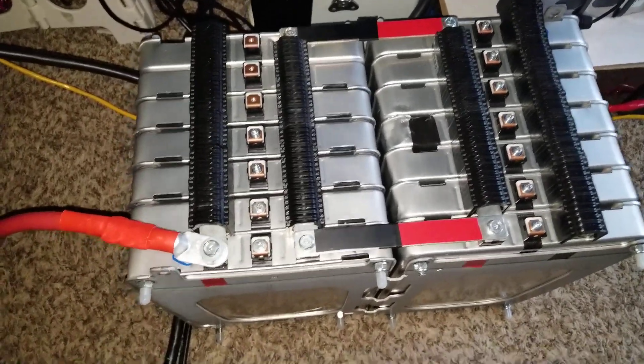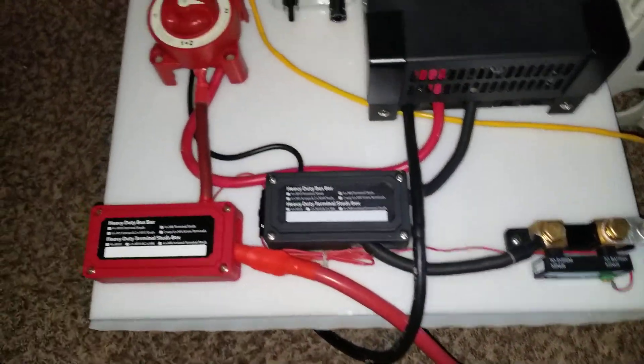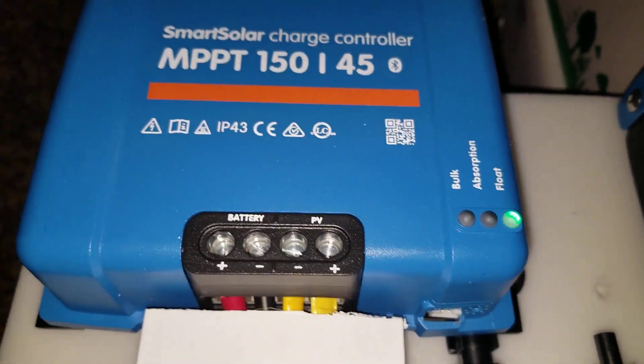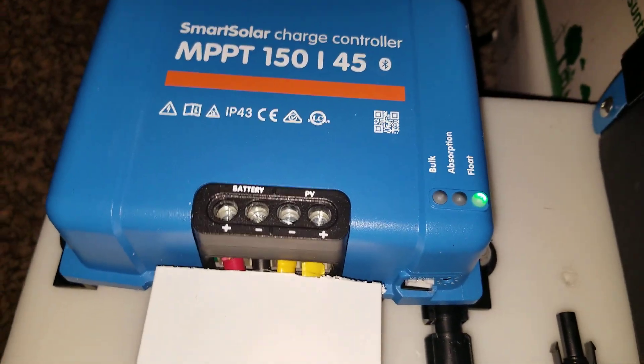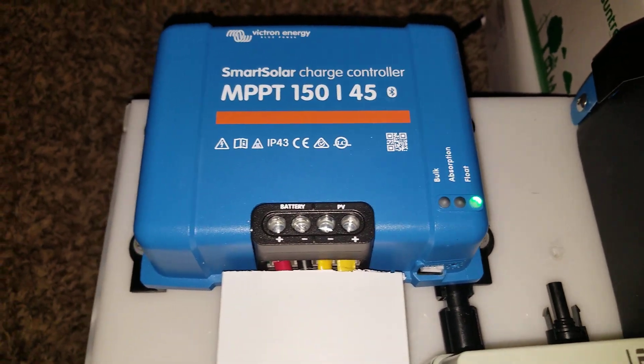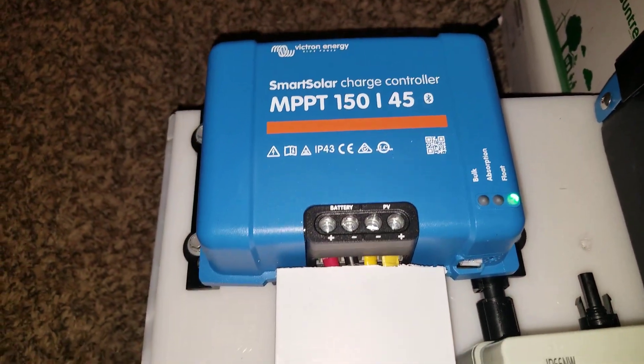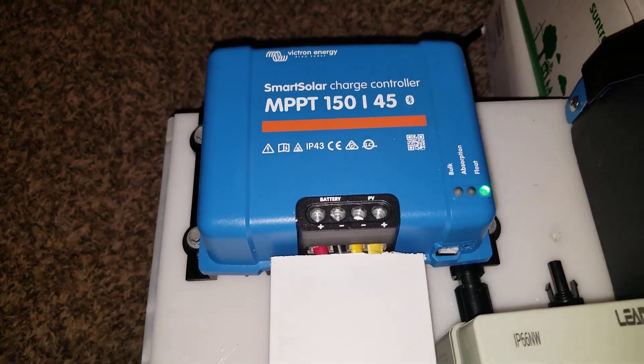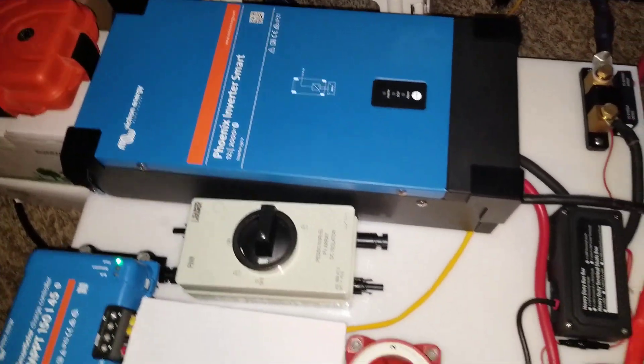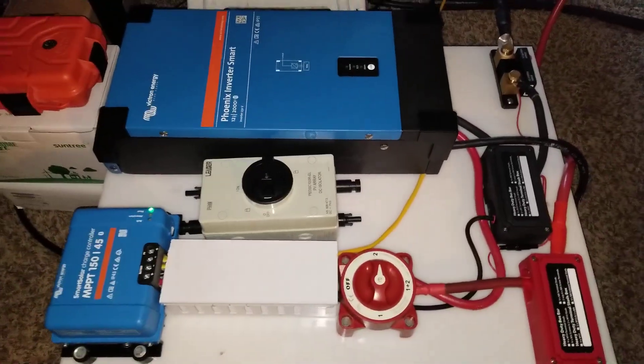And finally we got the batteries floated — you can see the light, the batteries are charged. So we're going to be doing a load test on these batteries to see if the 462 amp hours is what we can actually pull from them.